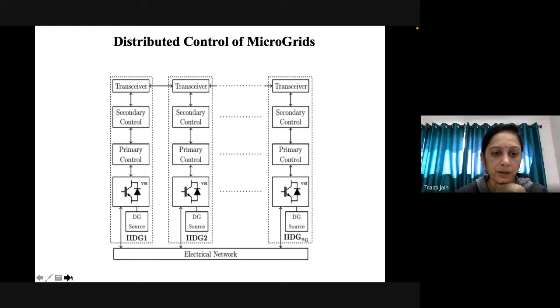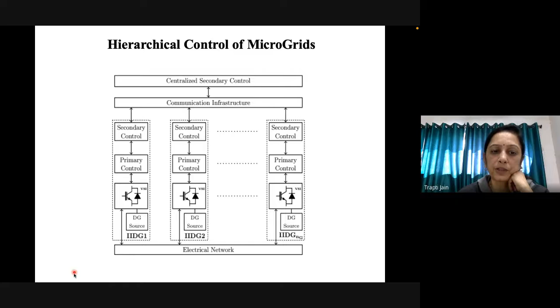Then comes hierarchical control of microgrids, which has two levels. We have local decentralized control, where each IIDG unit has its own secondary control, and it's also connected to communication infrastructure sharing information, with a centralized secondary control also used. So even if one fails, microgrid operation is still maintained. That is hierarchical control of microgrids.